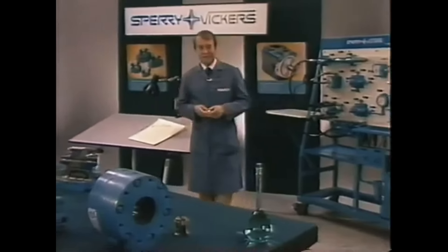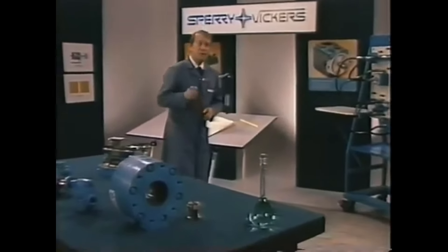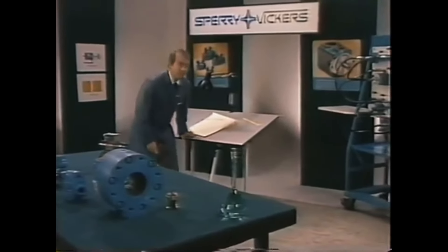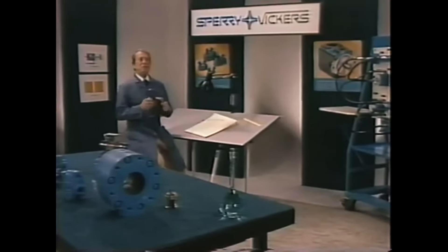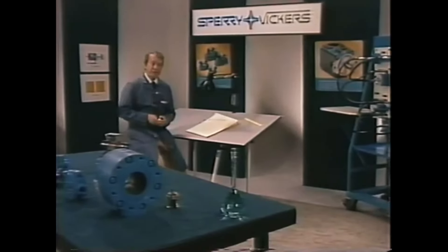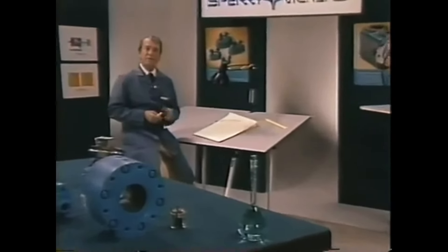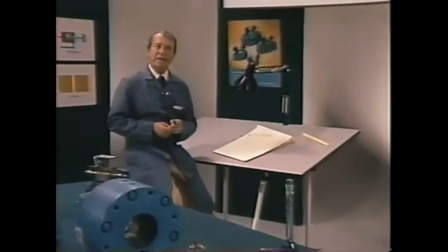Back at the start of this discussion, we used an electric motor to drive a pump, and you may have wondered, how big a motor? To determine this, we have to know how much force, or torque, was needed to do the job. That would tell us the pressure required and the size of the actuator. Then, knowing how fast the actuator had to move, we could determine the amount of fluid in gallons per minute that would be needed. Well, we have a formula to determine the horsepower required to move a given flow rate at a known pressure. You may want to make a note of it.